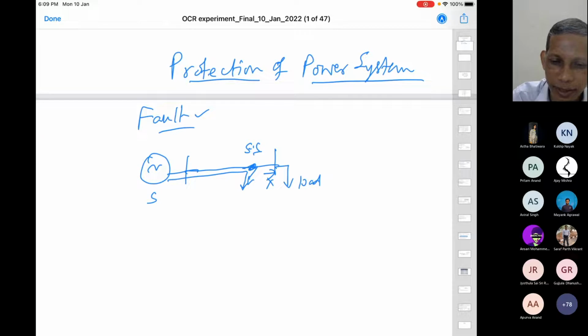So what happens here in this case, we generally in our terminology call it fault, that is when the current flows in an unintended path. Fault is that situation when the current flows in an unintended path. So this current, if we see here, the normal current, whatever the load was carrying. In this system, from here to here, the path, the conductor is designed or planned, the system is planned according to what may be the maximum load in the system. If you put something like very thick wire, then it will be costly, so it is not a proper thing.